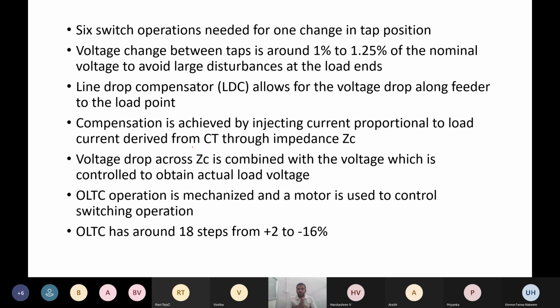So CT and PT are used mainly for the purpose of measurement, nothing more. They don't step up or step down any voltage levels. Just like our voltmeter or ammeter, we use CTs and PTs with their ratings. In the CT we observe one value of current. That current, which we actually are required to inject, will be injected through the tap changing transformers.